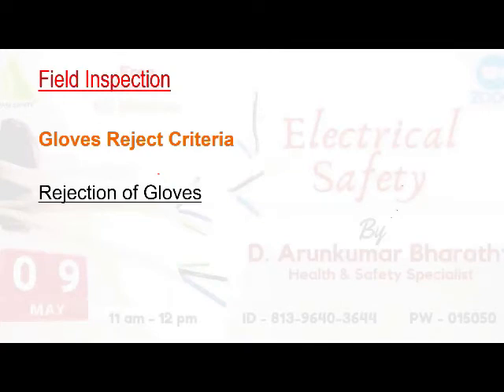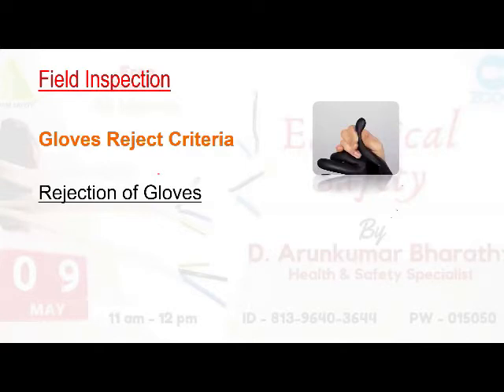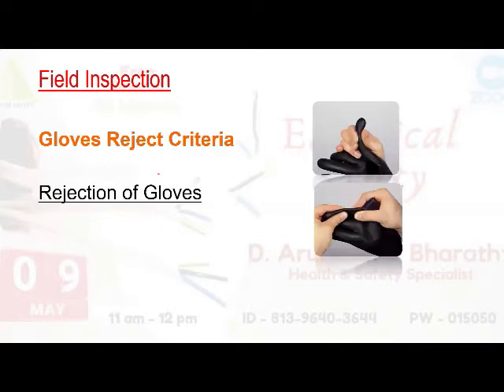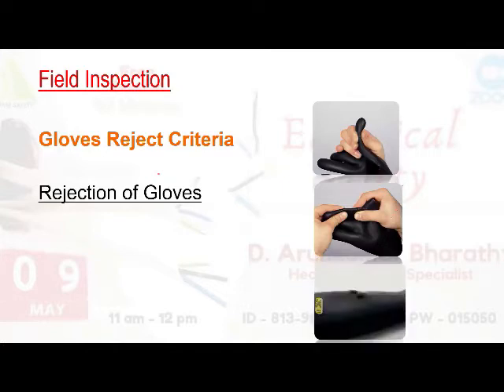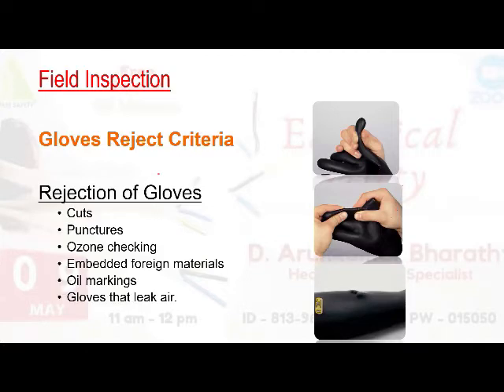What all inspection we have to do while using or before using the electrical gloves: we have to check all the fingers, and check the cuff, the wristy area, because that is the most vulnerable area to get cut or punched. You also have to check if there is any spillage of acids, chemicals, or other petroleum solvents, and check for the marking.